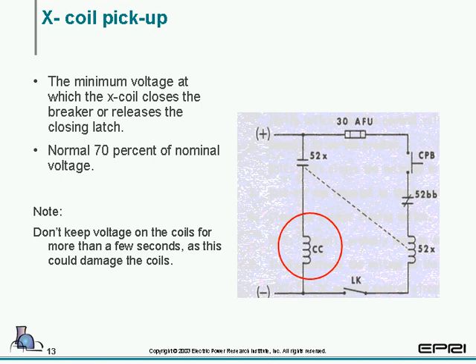The next couple of slides we're going to take a look at are actual coil values. Now the X coil is your closing coil. In this particular design, it's also called the CC coil. Normally, the breaker operates under normal operating conditions. What we find is the best way to test it is normally at 70% of that nominal voltage. But you don't want to keep voltage on that coil longer than a couple of seconds.